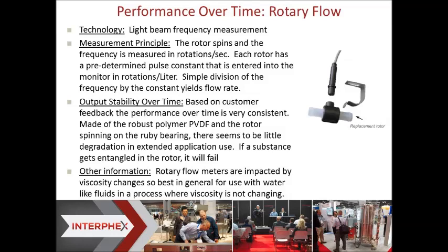The rotary flow meter measures rotations of a rotor that's within the sensor, and the rotor rotations are counted by a beam, and each one of these flow cells has a constant called pulses per liter, and the rotations are divided by the pulses per liter and gives you flow. The one downfall of this product is if something would get entangled into the rotor over an extended period of time, it's a frictionless rotor, and if anything gets entangled, it will stop turning. And also, rotary flow technology can't be used if viscosity is going to change in the process. The K factor is based on the specific viscosity of water-like materials.